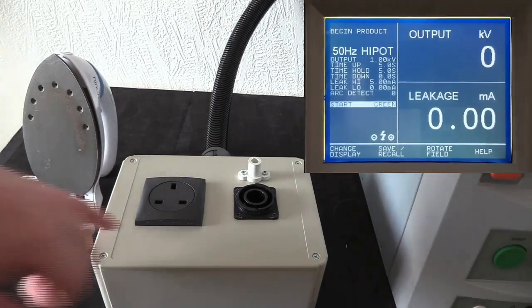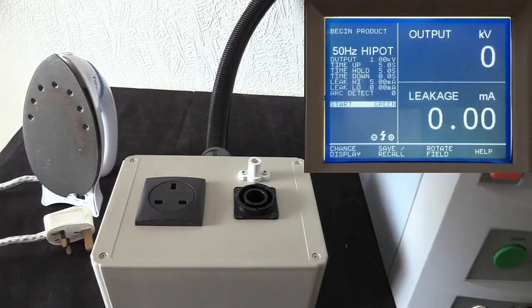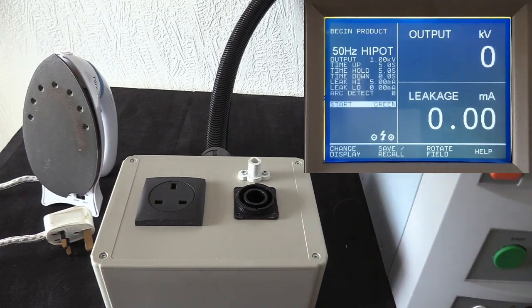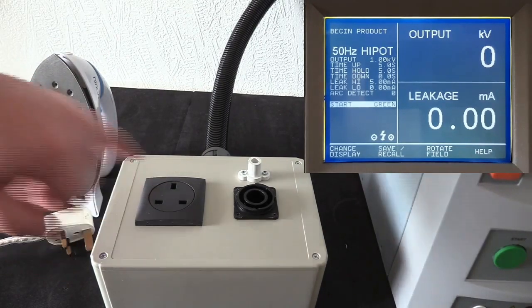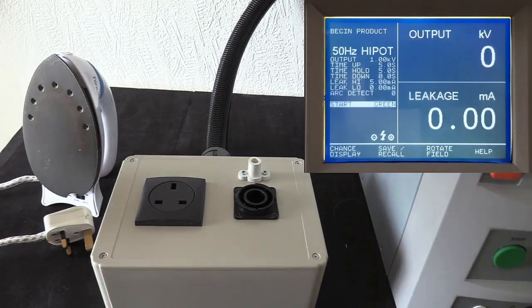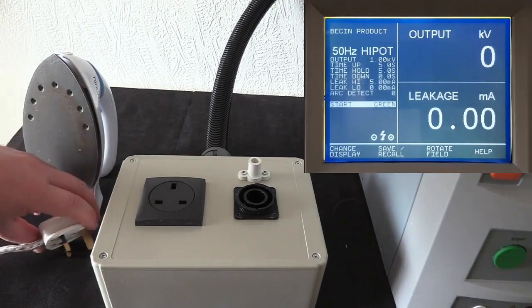Now, during testing, what will happen is the live and neutral connectors will be linked together. The test voltage will be applied to the live and neutral conductors simultaneously. And then any fault current returning to the HAL will go via the earth cable of the appliance. So let's plug the unit in and perform the test.